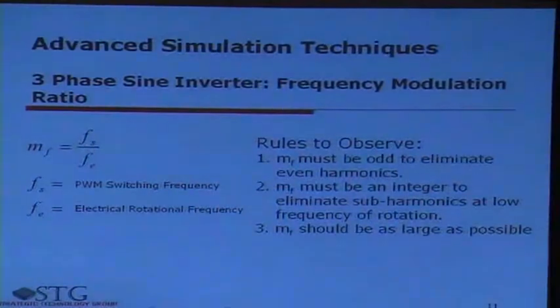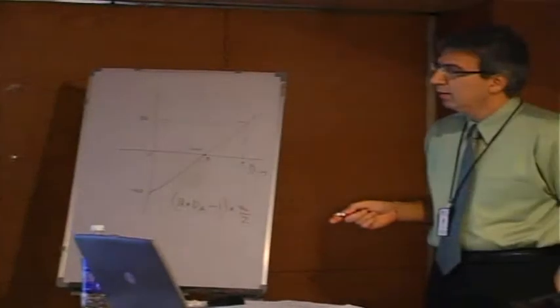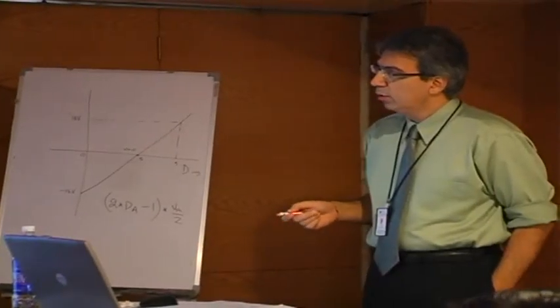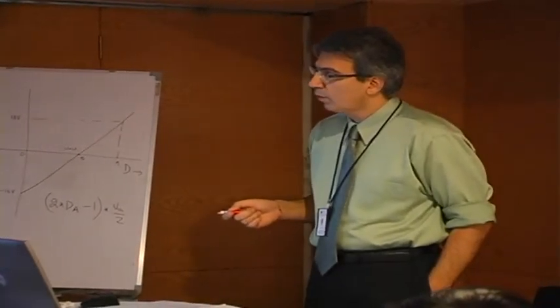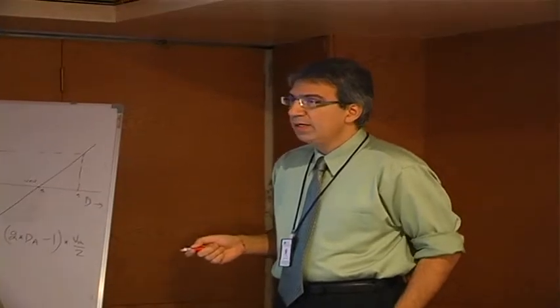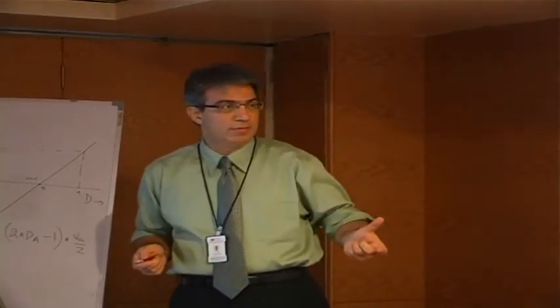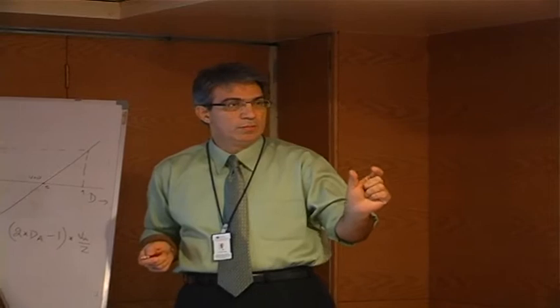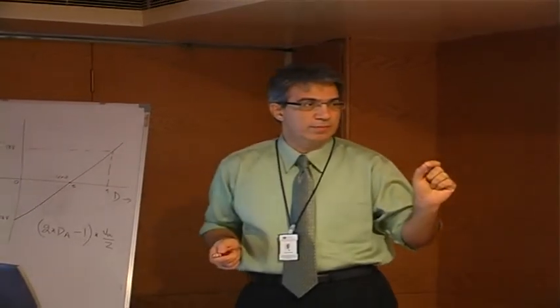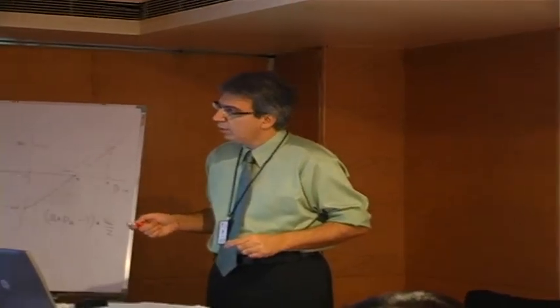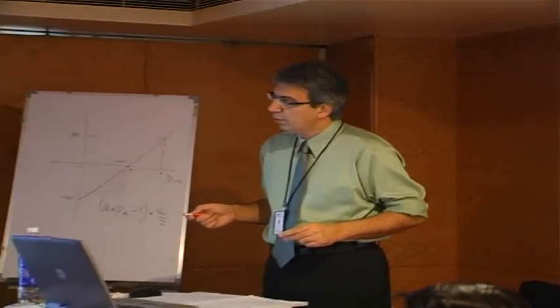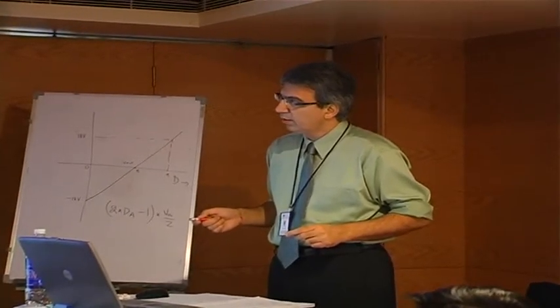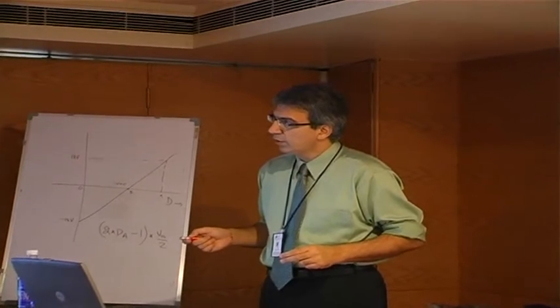So talking about the frequency modulation, this becomes important because here you have, depending upon the speed of your drive, you want to pick the switching frequency. And the ratio between the switching frequency and the electrical rotational frequency is frequency modulation ratio.